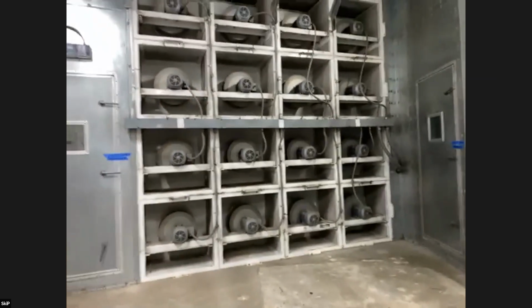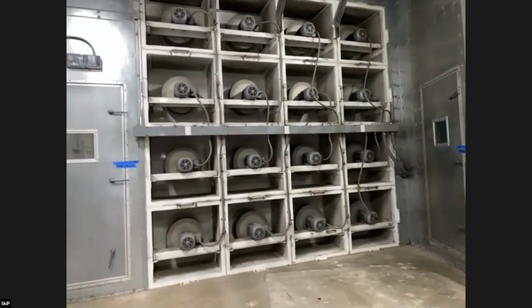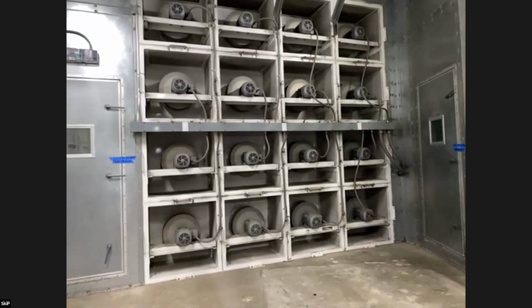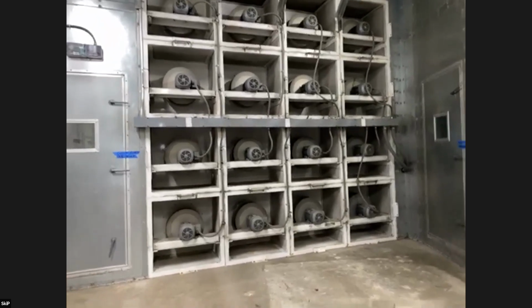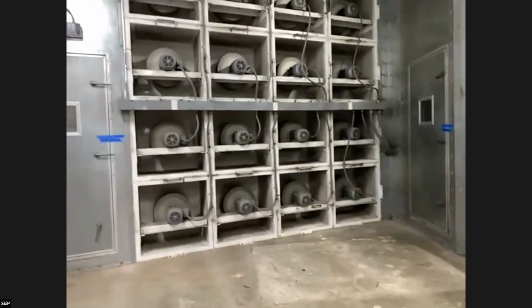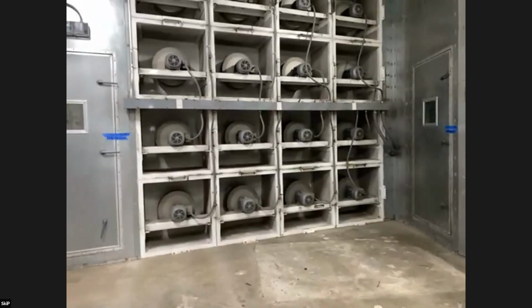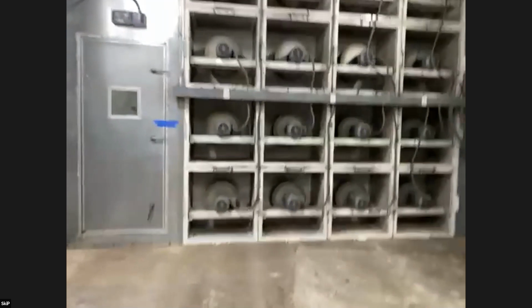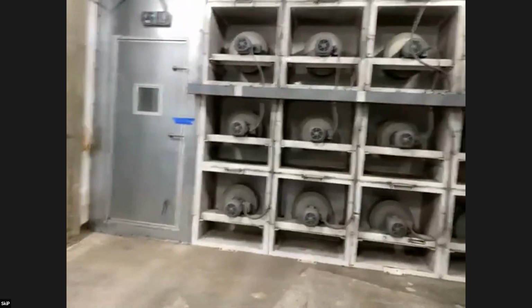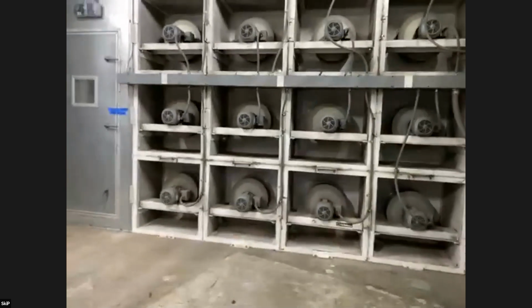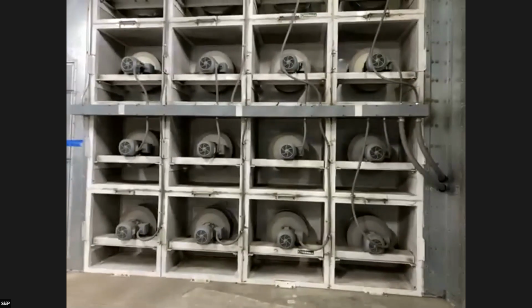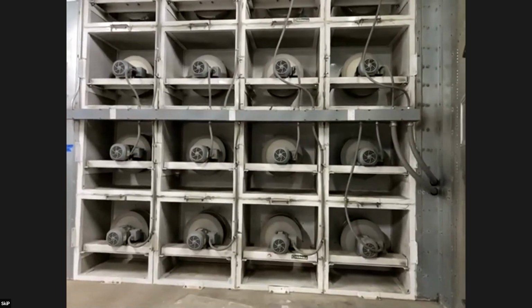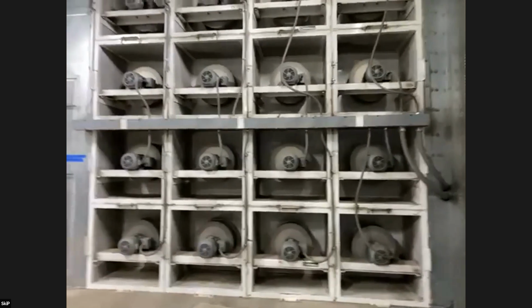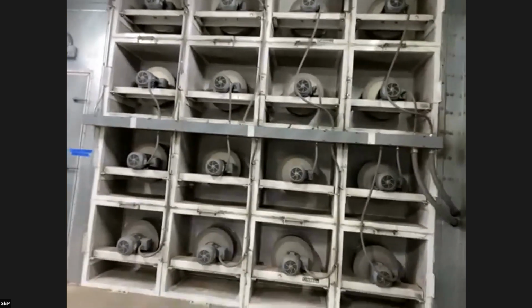What that does is it makes it so that the doors open and close correctly. If we didn't have that balance, like if this fan wall, the return, were to shut off, then it would be hard to shut the doors because the supply would be blowing all the air into the space like a balloon. And if we don't return any of it, then it tries to get out wherever it can, and so the doors would be pushing open. At the same time, if we had the return running and not the supply, then the doors actually get really hard to open because they're sucked shut because it's sucking air.